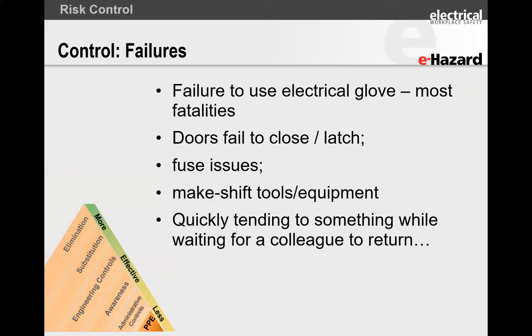What are the practical PPE failures? We fail to use electrical dielectric gloves with protectors over them. We have doors that may not close or latch correctly and we try to fix them — but fixing that door that hasn't closed is actually a scope change. If you went to troubleshoot and the door's not closing and you try to close it, it is a scope change. Fusing issues — may not have the right size fuse, may not have fuse pullers.